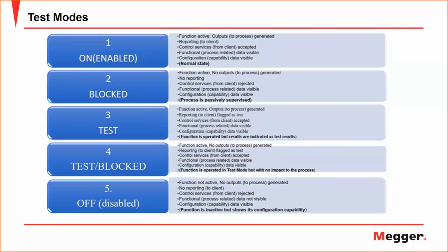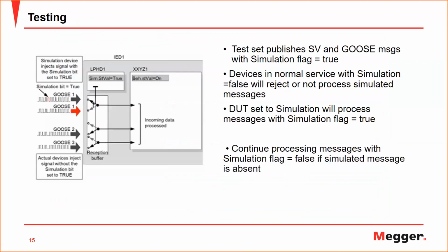And the last mode is being off, which means a logical node or function is completely off. It's not accepting any inputs, processing anything, or generating any outputs. So it is very important to understand this test mode when you want to do testing.